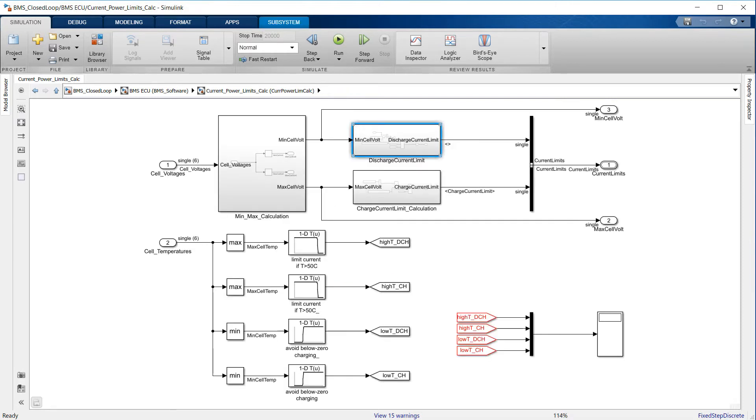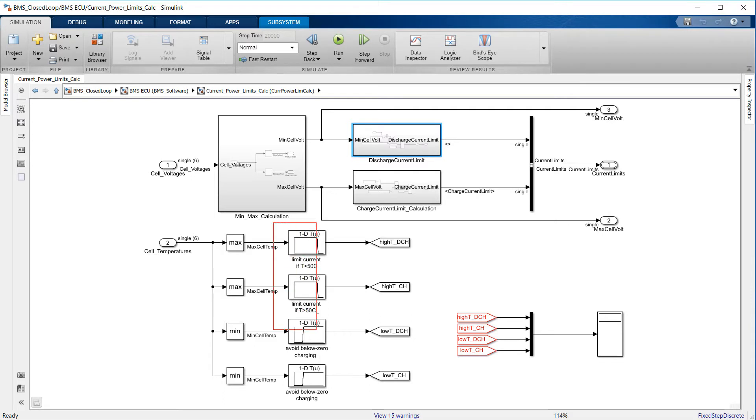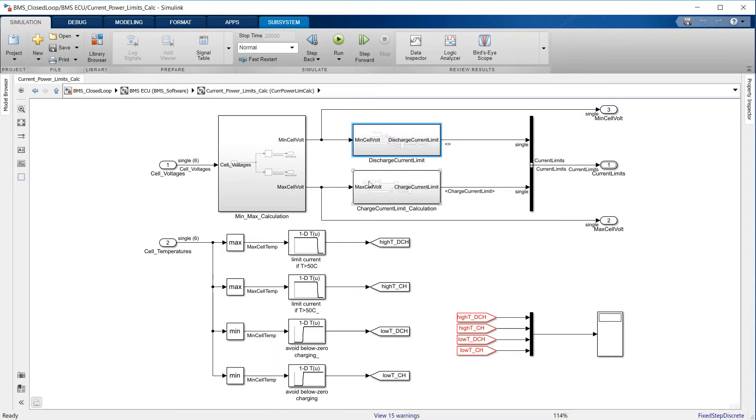We also know that it is important to limit current delivery or intake when temperature is too high or too low. Using a lookup table with a rising or falling S-shaped profile, we can specify a current threshold based on temperature and modulate the allowable current delivery. This is very important to avoid physical damage to the cell materials at high temperatures, both during charge and discharge, and at low temperatures during charge, since doing so below freezing temperature is not allowed.